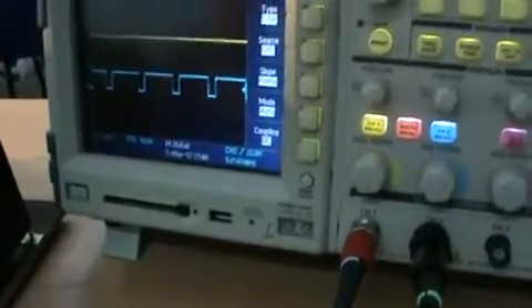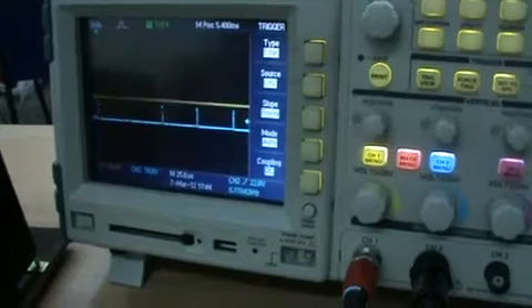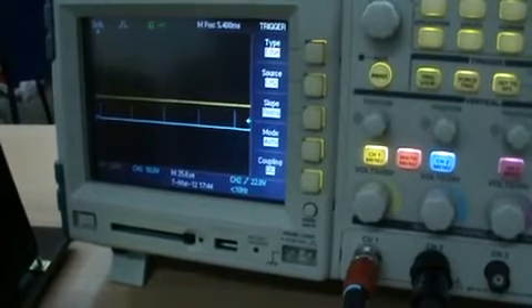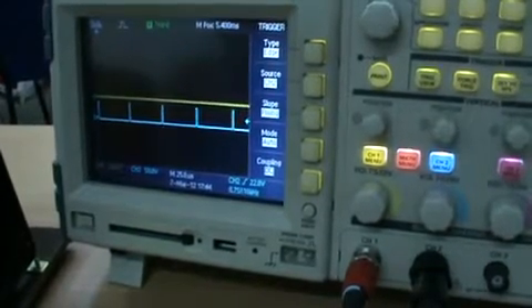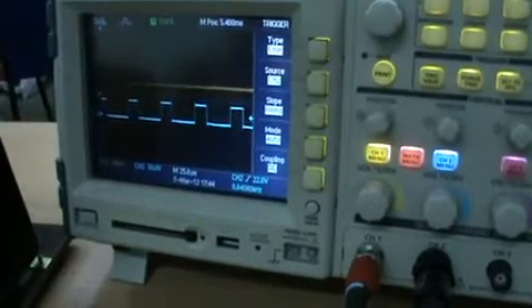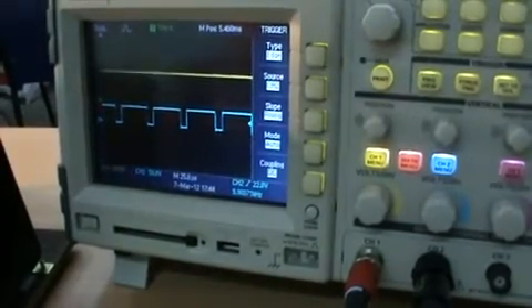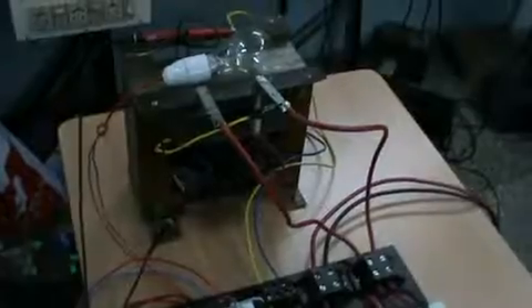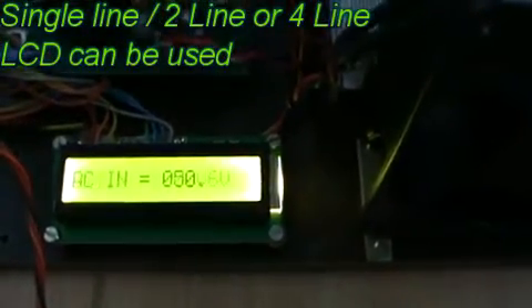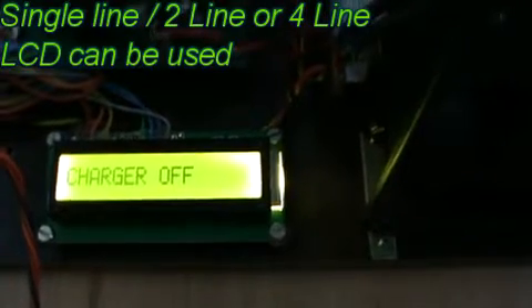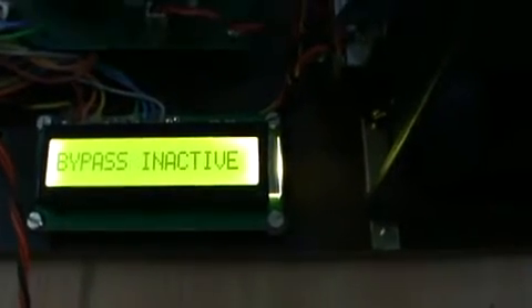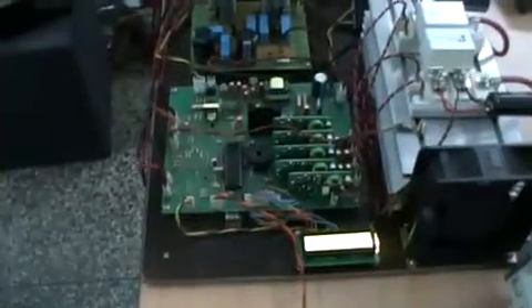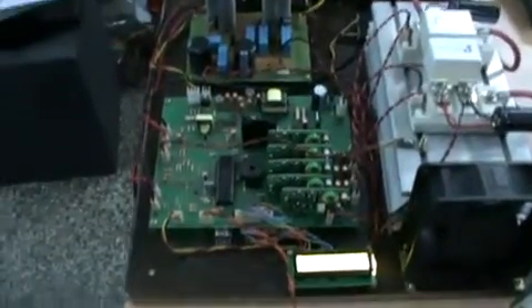During soft start, you can see the PWM in blue is increasing, and at the same time the output voltage in yellow is also increasing. The LCD will display all the parameters such as battery voltage, AC input, charger status, bypass status, load, etc. The inverter has all protection against overload and short circuit.